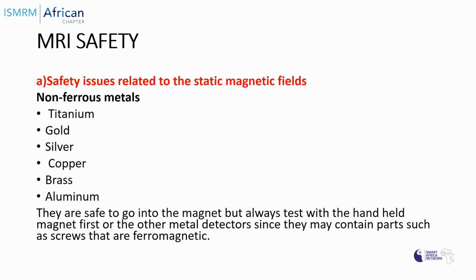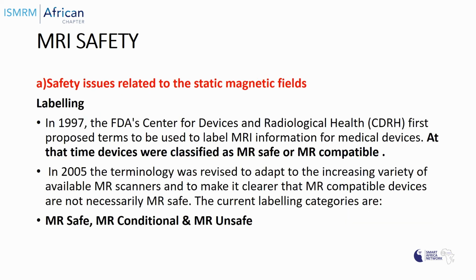Now, what are the non-ferrous metals that are safe? We can use titanium, gold, silver, copper, brass, and aluminum. They are safe to go into the magnet, but always we need to test with the handheld magnet first or the other metal detectors, since they may contain parts such as screws that are ferromagnetic.